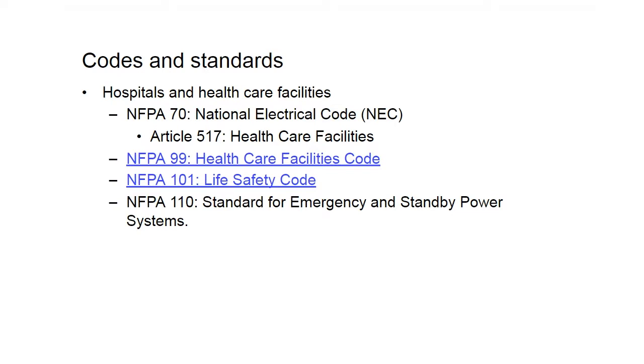There's been a lot of efforts over the last several iterations or code cycles through these various codes themselves to try to bring alignment between the codes. The technical committees that have been working on these have realized over the course of the years that there was contradictory information. So in the past couple of code cycles, there's been quite a bit of alignment, particularly between Article 517, NFPA 99, and NFPA 110.